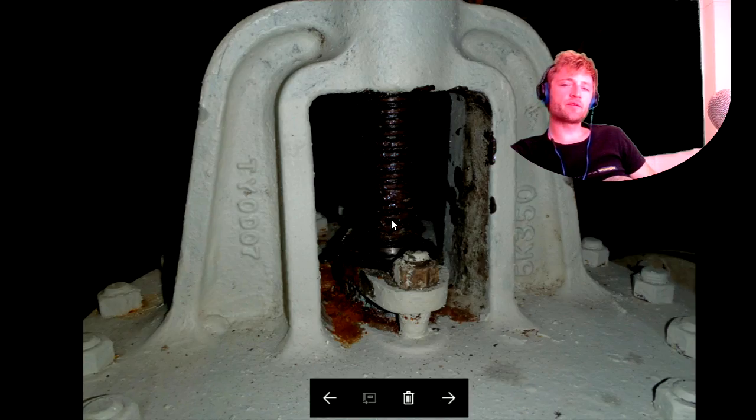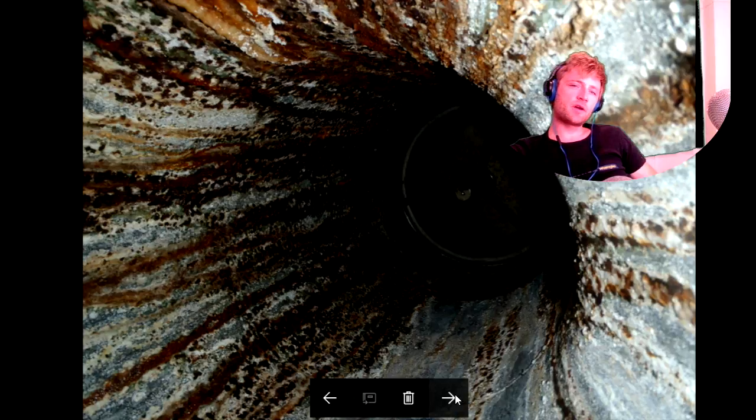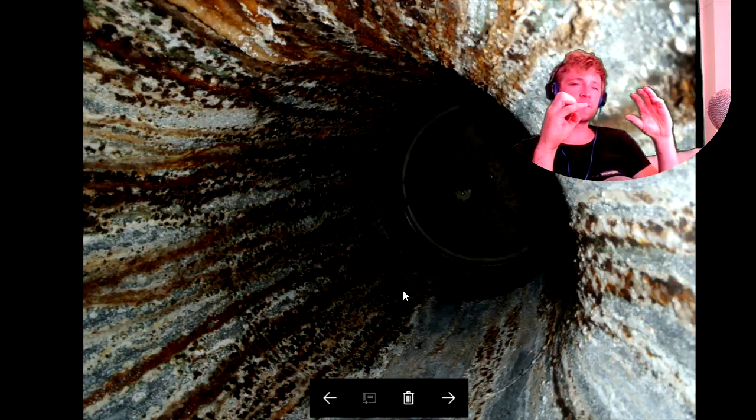Lubricate the shaft here and check if there are any leakages. This is a very, very big valve — really big. It weighs about one ton, something like that. And this is how it looks from inside. As you can see, there is rust from humidity — the water is trapped. Because water, as we know, evaporates and goes up.